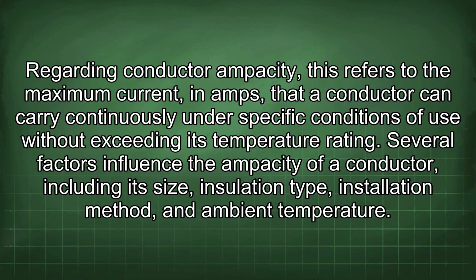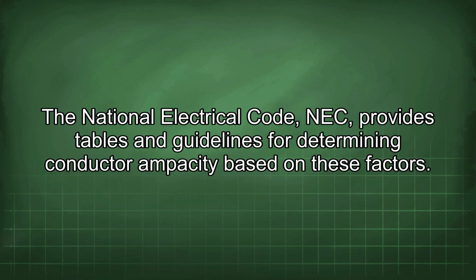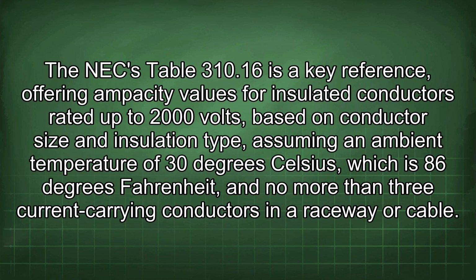Regarding conductor ampacity, this refers to the maximum current in amps that a conductor can carry continuously under specific conditions of use without exceeding its temperature rating. Several factors influence the ampacity of a conductor, including its size, insulation type, installation method, and ambient temperature. The National Electrical Code (NEC) provides tables and guidelines for determining conductor ampacity based on these factors. The NEC Table 310.16 is a key reference, offering ampacity values for insulated conductors rated up to 2000 volts, based on conductor size and insulation type, assuming an ambient temperature of 30 degrees Celsius, which is 86 degrees Fahrenheit, and no more than 3 current-carrying conductors in a raceway or cable.